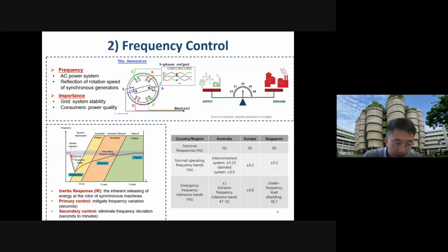Now, for this initial period, how fast the frequency will decline and how low it will decline depends on the system's inertia response. Because the generators are rotational machines, they have inertia. After the balance is broken, the kinetic energy in the rotor will be released, so the frequency will gradually decline until the lowest point, the nadir. Then after that, the frequency will be gradually recovered by the system control systems, including the primary control system and then the secondary control system. These two control systems will gradually recover the frequency.